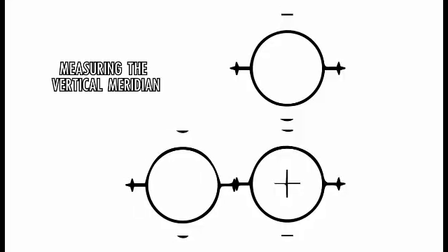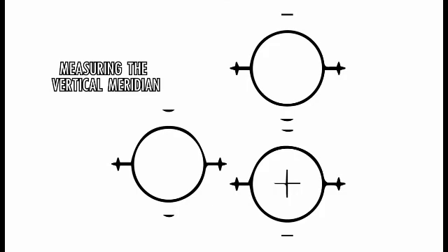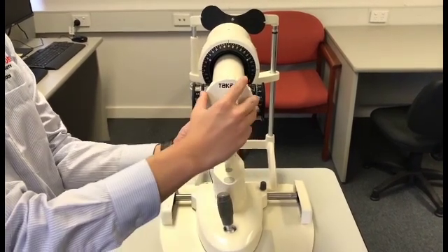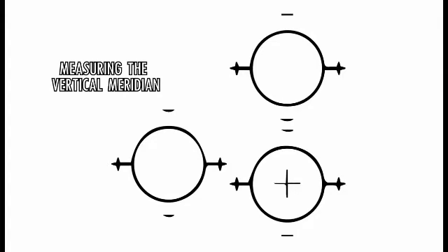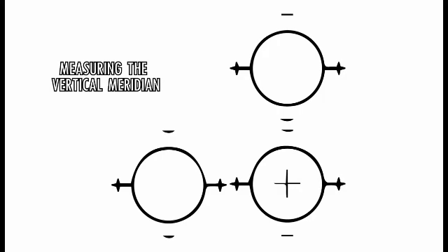The scale on the right-hand drum indicates the actual dioptric power of the corneal curvature in the vertical or near vertical meridian. With an astigmatic cornea, it is impossible to get both principal meridians in focus at the same time. Turn the horizontal measuring drum until the plus signs are barely separated. If the horizontal lines of the plus appear continuous and unbroken, the instrument is set at the position of the axis of the astigmatism. If they appear discontinuous, the keratometer is not at the cylinder axis. Rotate the entire tube while looking into the eyepiece until the horizontal lines of the plus signs appear continuous and unbroken. A further check may be obtained by throwing the instrument slightly out of focus with the focusing knob.